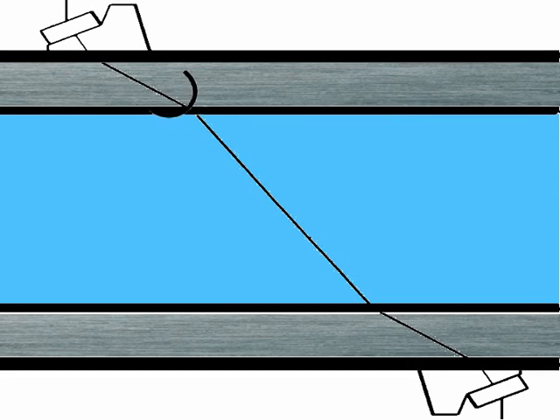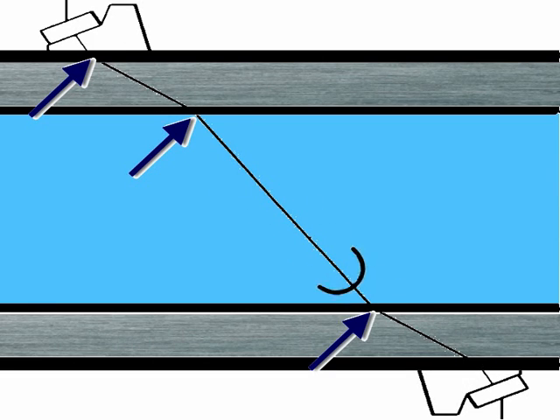For us to get both of these signals across, we have to firstly place the transducers very accurately on either side of the pipe. To do this, the refraction angles of the ultrasonic signal as it passes from one medium to another need to be known.